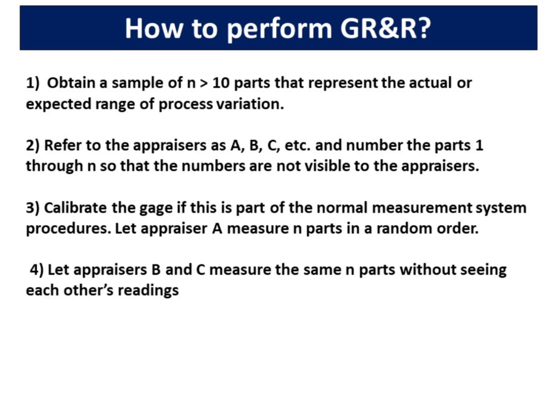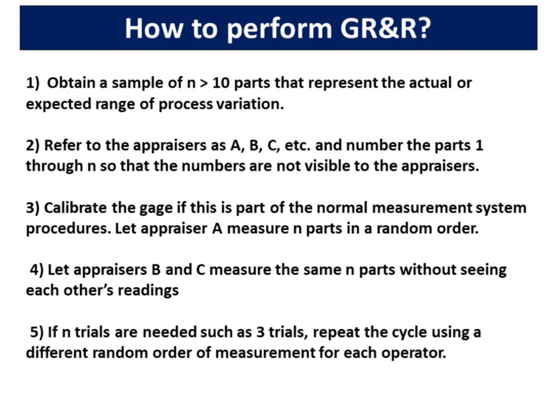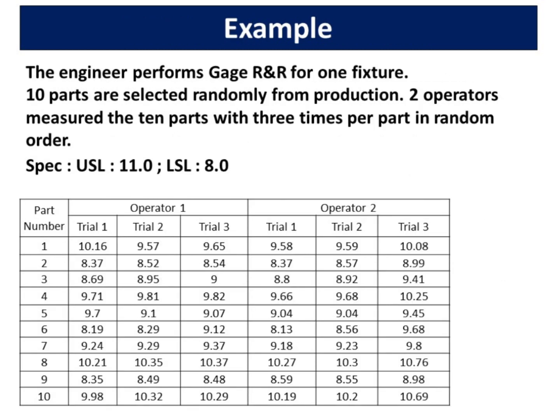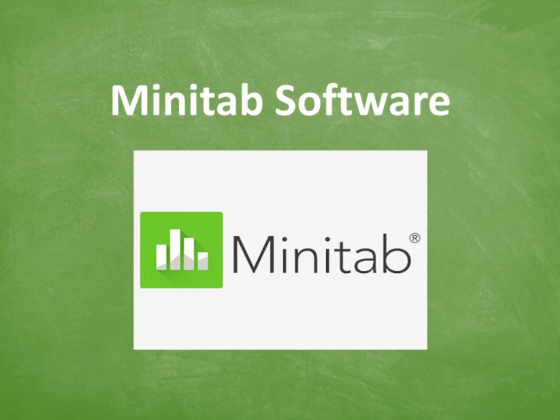Step 3: Calibrate the gauge if this is part of the normal measurement system procedures. Let appraiser A measure N parts in a random order, and let appraisers B and C measure the same N parts without seeing each other's readings. If multiple trials are needed, such as 3 trials, repeat the cycle using a different random order of measurement for each operator. For example, the engineer performs gauge R and R for one fixture: 10 parts are selected randomly from production, 2 operators measured the 10 parts 3 times per part in random order. The upper spec limit, USL, is 11 while the lower spec limit, LSL, is 8.